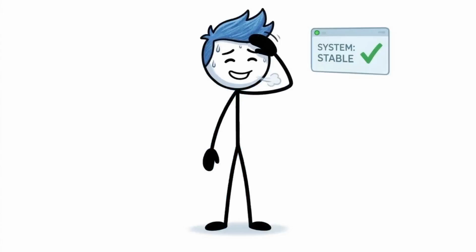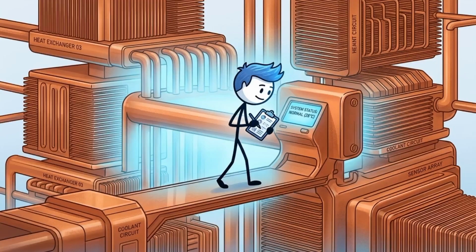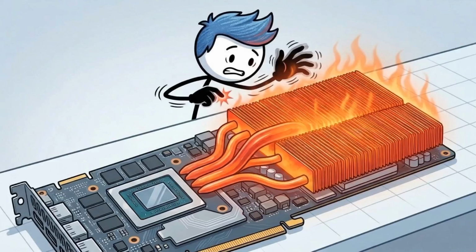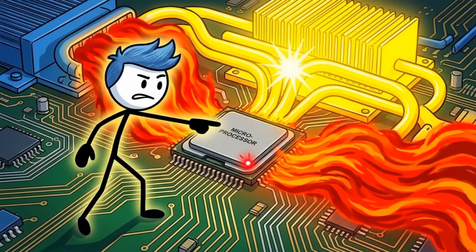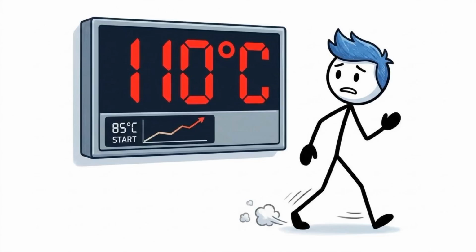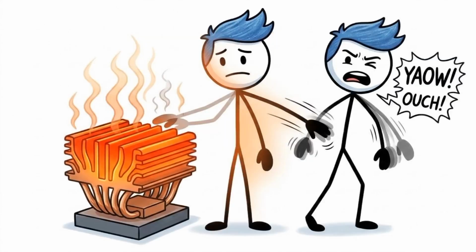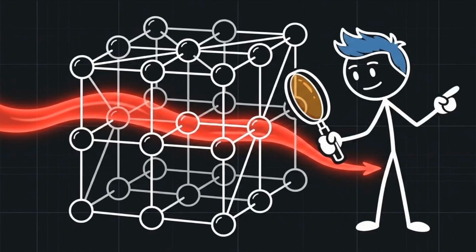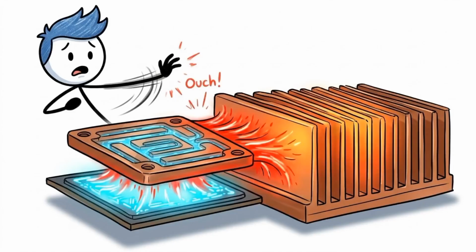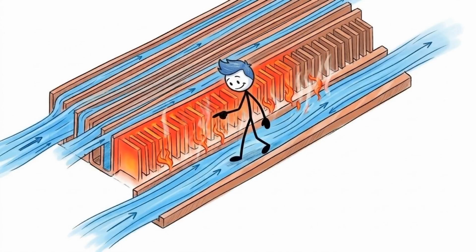But let's assume the substation holds. The power gets through to the server room. Now the hammer hits the liquid cooling loop. Because those thousands of chips heat up almost instantly, the temperature of the silicon spikes to 85 degrees Celsius in less than a second. Under standard thermodynamic designs, the copper heat sinks are supposed to absorb this initial shock and transfer it to the water loops.